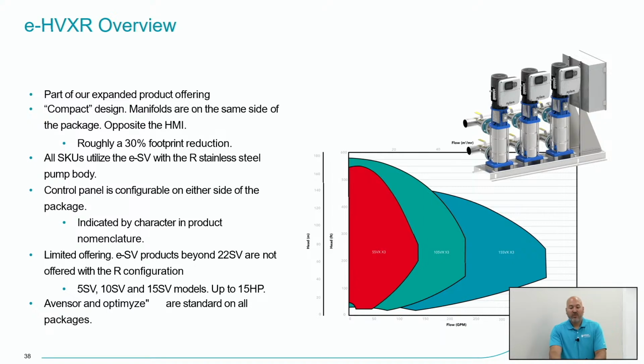So what we've done is created the e-HVXR. Now the suction and discharge manifolds are on the same side of each other, right? You can see them on top of each other there, giving us a 30% reduction in footprint. And the whole idea here is now if you're using this R configuration, these will fit through a standard doorway for you. So now you can get them into those tight spaces. You don't have to do some work out in the field by taking off the manifolds and putting them back on.